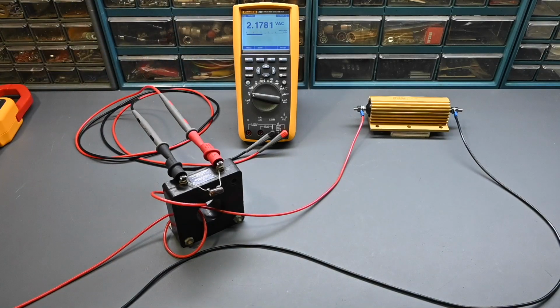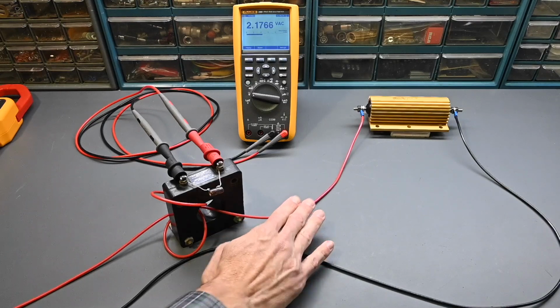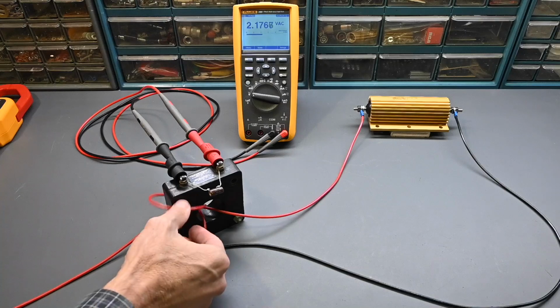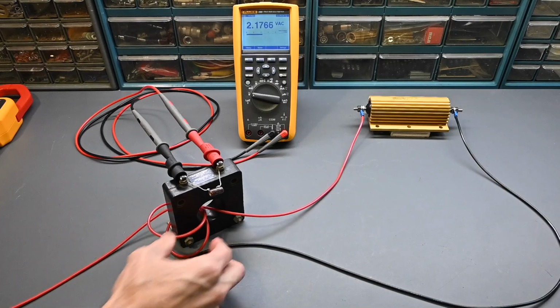And that's the effect that I was mentioning on the current clamp as well. If you loop the wire multiple times through the jaws of the current clamp, you'll get a higher reading, and it just basically becomes more sensitive. So if this was a very, very low current and you needed to have it more sensitive, you could have multiple turns going through the transformer.